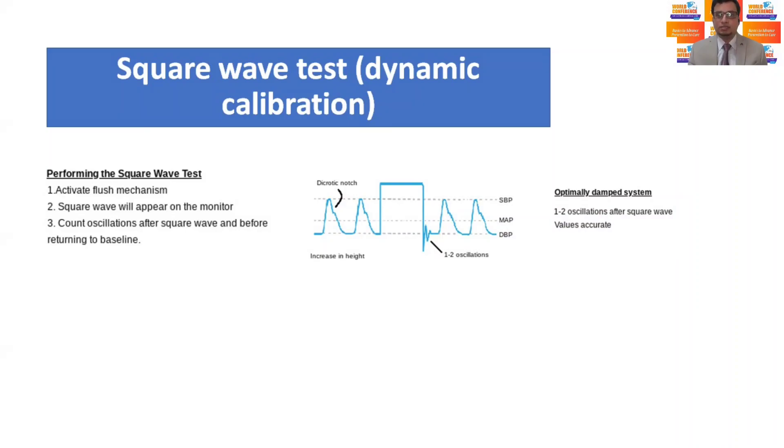The natural frequency of the system may be measured in the clinical settings using the fast flush test or square wave test. The system is flushed with the high pressure saline via the flush system. This generates an undershoot and overshoot of waves resonating at the natural frequency of the system. Now count the number of oscillations after the square wave.